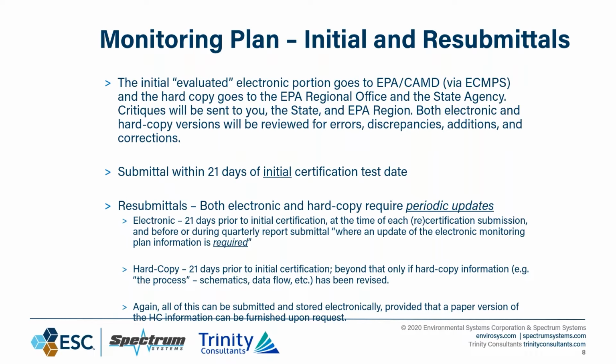Any critiques, comments, or observations get sent to you, the state, and your region. Both portions of the monitoring plan get reviewed for errors, for discrepancies, for anything that needs to get added or corrected. A hard date on that is that the submittal needs to occur within 21 days of your initial certification test date.